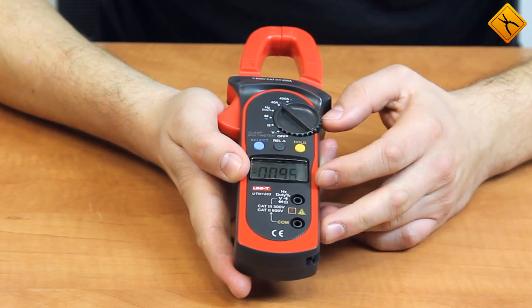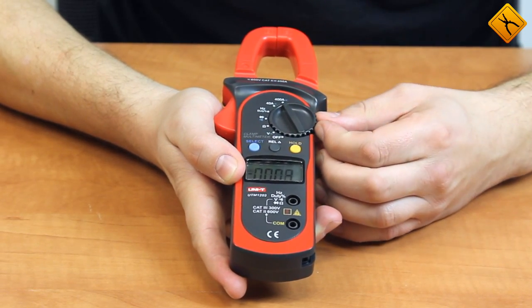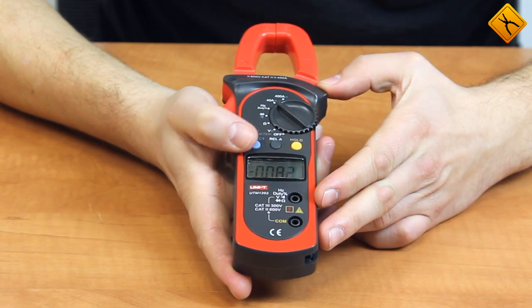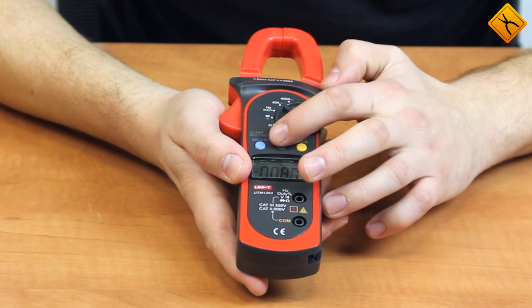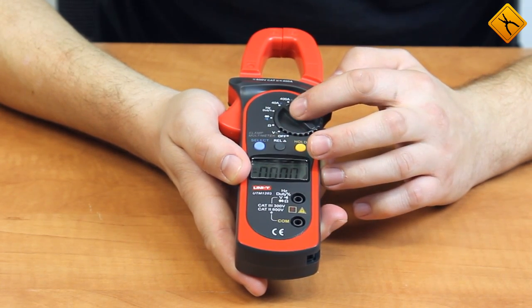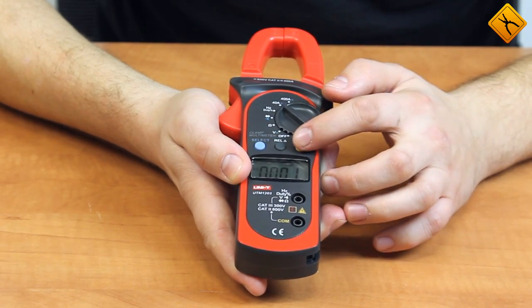Here we have the current measurement mode. There are two measurement ranges available — 40 amps and 400 amps — and they are both selected manually. The select button allows you to choose the type of electrical current. The REL button corresponds to the relative measurement mode, which is vital for direct current measurement. There is also a hold button for fixing measurement results.